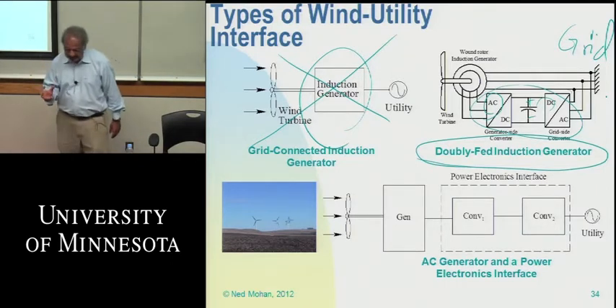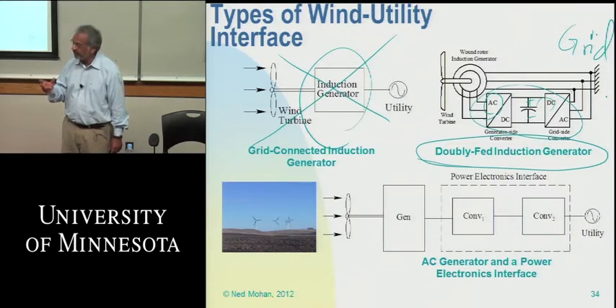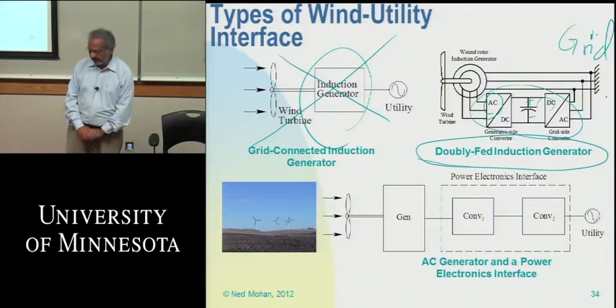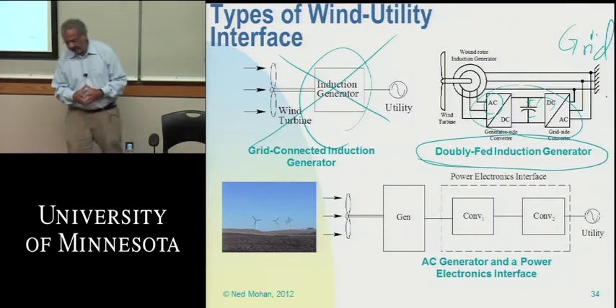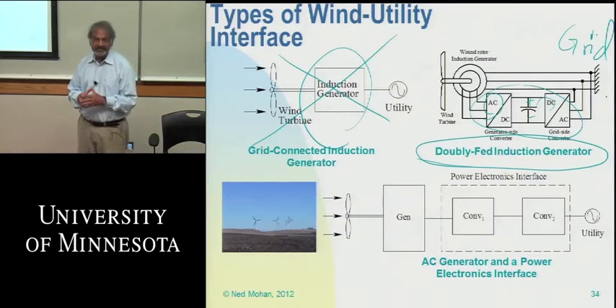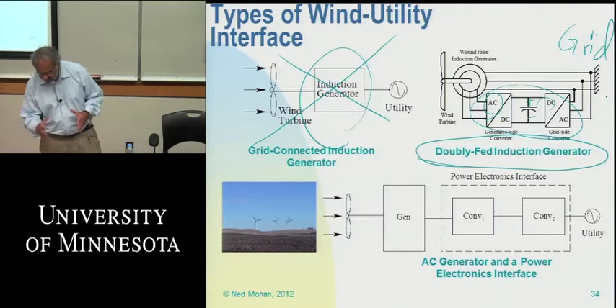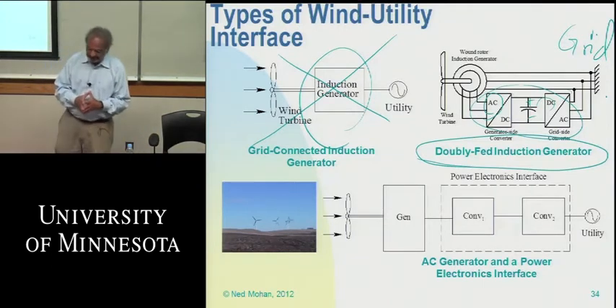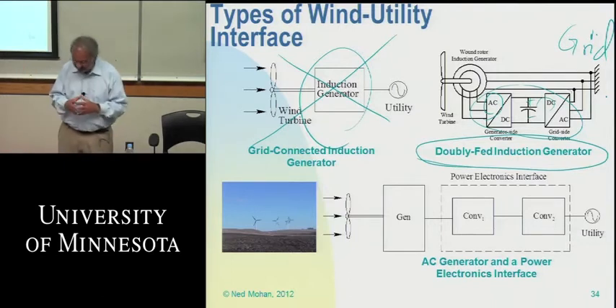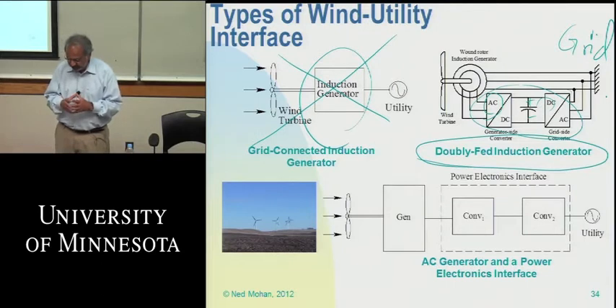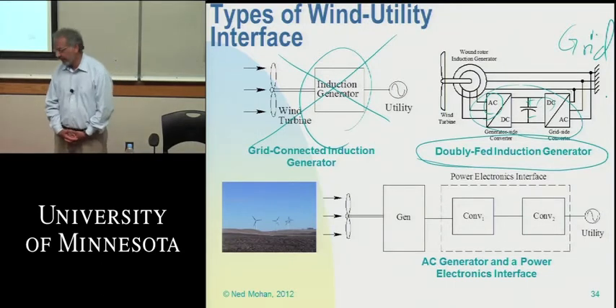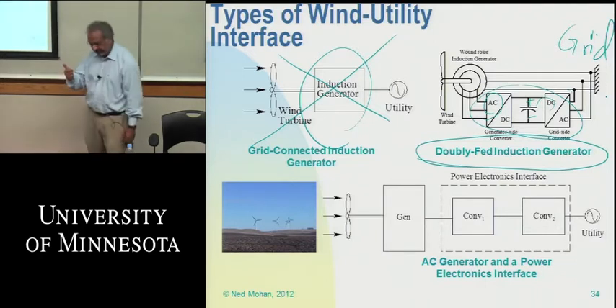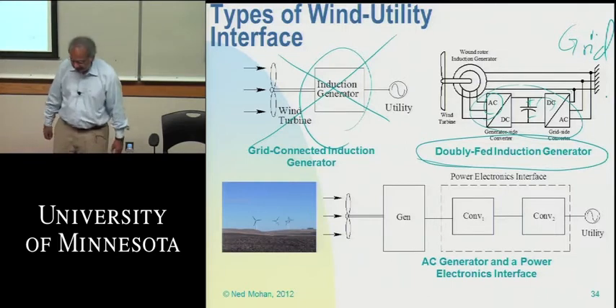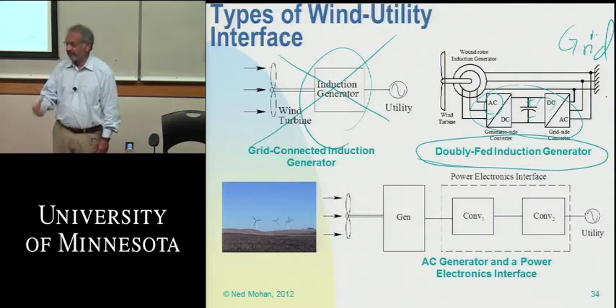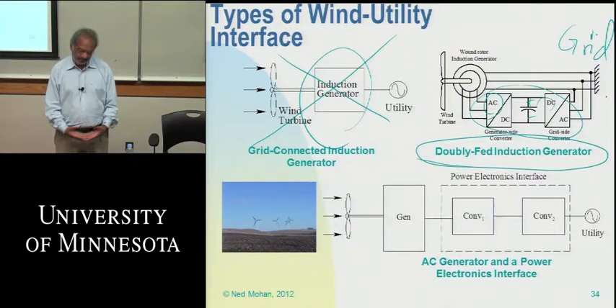So power electronics is only 15 to 20% of the rated generation capacity of the machine. Okay, and power electronics is still expensive. So these doubly fed induction machines are still used. The disadvantage is that you have only a limited range of speed in which you can control these generators, beyond which you'll exceed the rating of this power electronics too much, and then all the advantages would disappear. Okay, so you're limited in speed over which you can control it, and the other disadvantage is that you have slip rings and brushes in the rotor circuit. There's a mechanical contact, not very desirable.